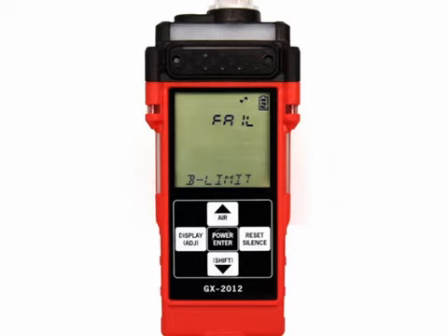If the unit is due for bump testing and the bump expired is set to not use, then the fail bump limit prompt is displayed. At the same time, the alarm LEDs and buzzer will pulse several times. The fail prompt will remain on the display until the unit is turned off. The GX-2012 cannot be used until a complete bump test has been performed. If bump testing is not due or bump expired is set to no effect, then the display will indicate when the next bump test is due.